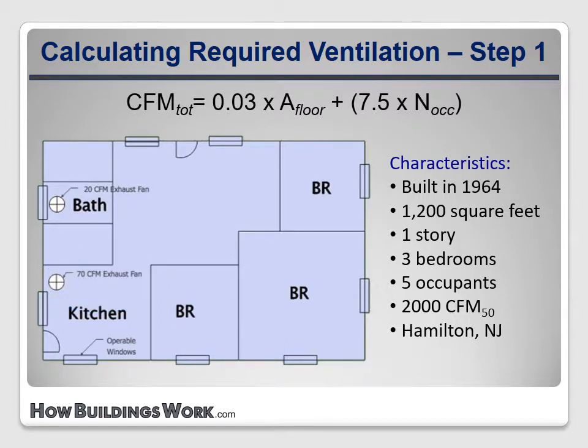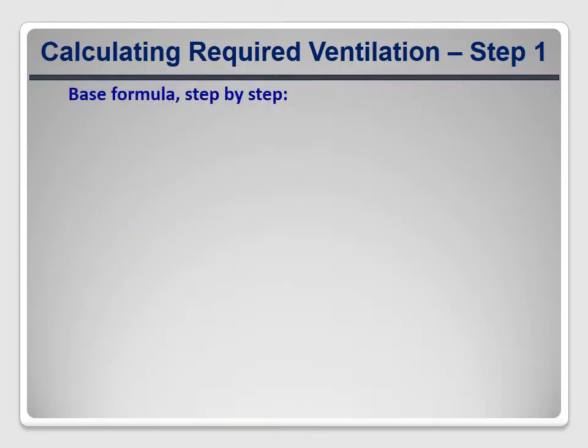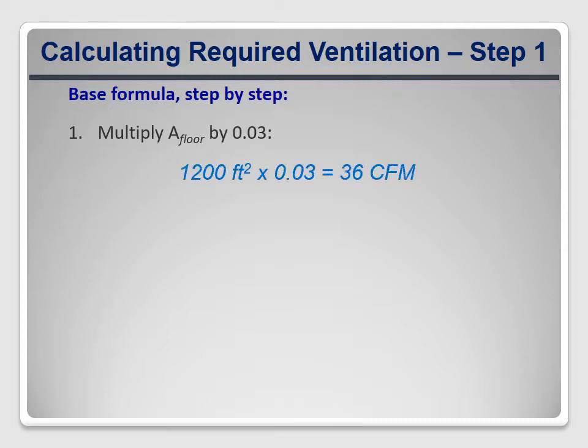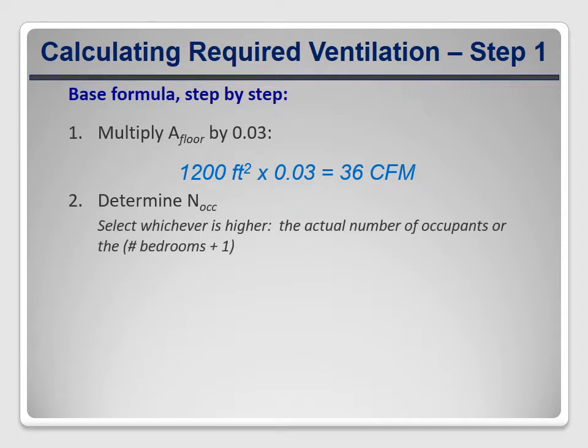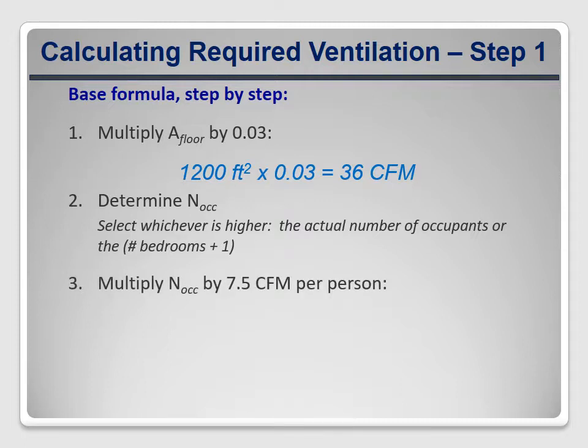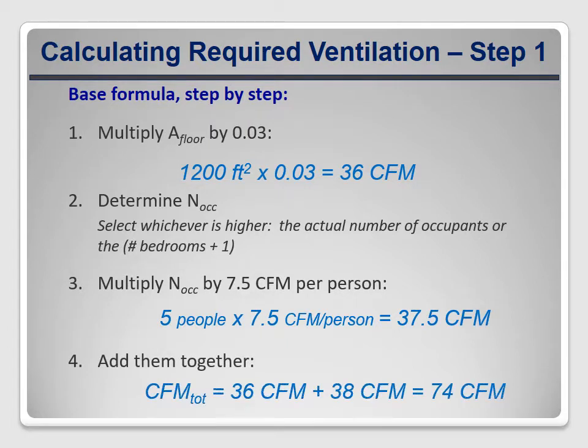Just like the new construction example, our first step is to calculate the total desired ventilation rate. The first part of the equation deals with floor area, so we multiply 1200 square feet by 0.03, giving us 36 CFM. For the second part, we consider occupants: there are five, which is higher than three bedrooms plus one, so we multiply five occupants by 7.5, giving 37.5 CFM — rounded up to 38. So we need 36 plus 38 for a total of 74 CFM of total desired ventilation.